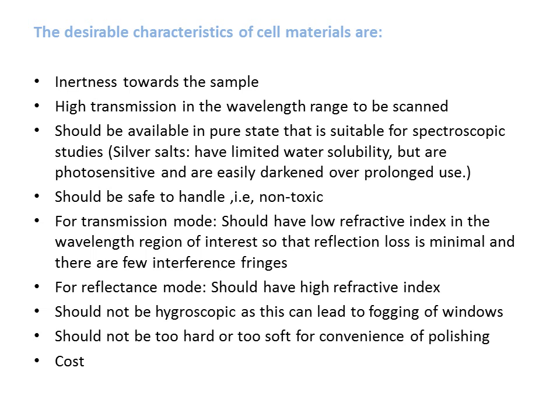It should be non-toxic. If it is used in a transmission mode, the substance should have a low refractive index, and if you are studying the sample in the reflectance mode, the substance should have a high refractive index. It should be non-hygroscopic preferably. If it is hygroscopic, it can result in fogging of the windows. And if you have fogged windows, they have to be polished.